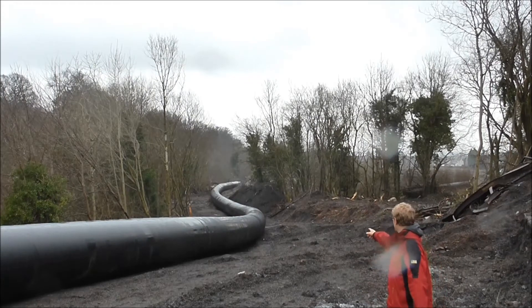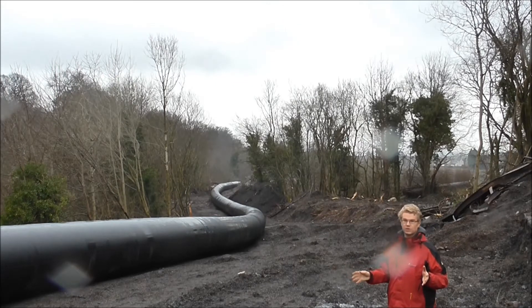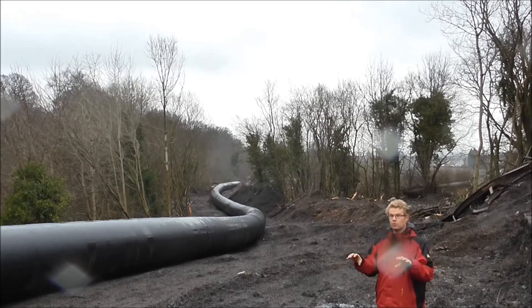The pipe that we're putting together now has to be able to carry 3,000 litres of water every second coming in at the top when it's at full capacity. That's a high volume for what is a relatively small hydro station. The pipe itself is 600 metres long and 1.4 metres in diameter, made out of high density plastic which is butt-welded together, so we have a large piece of kit with two big clamps.